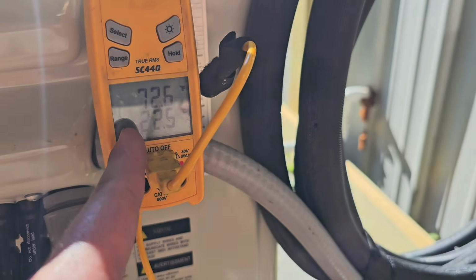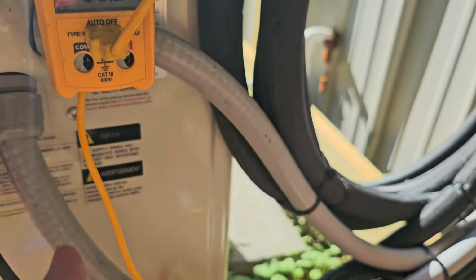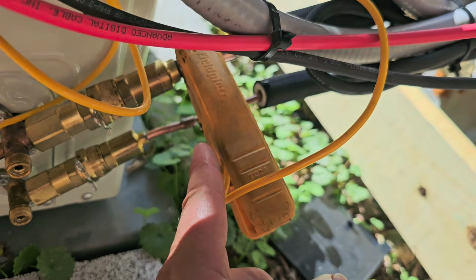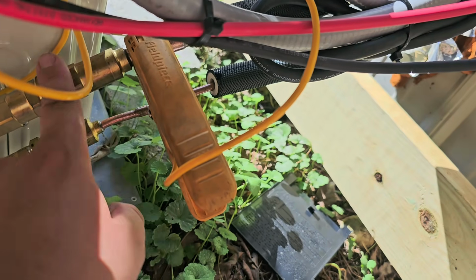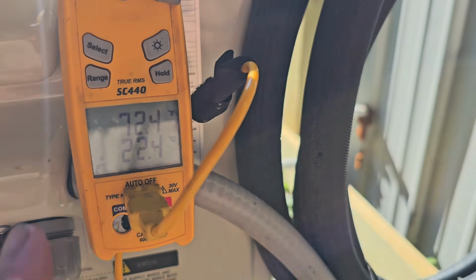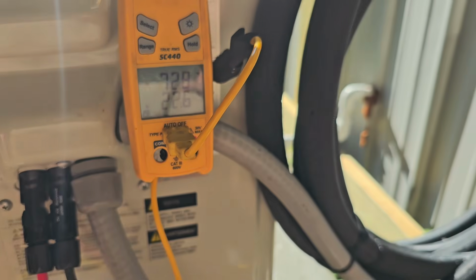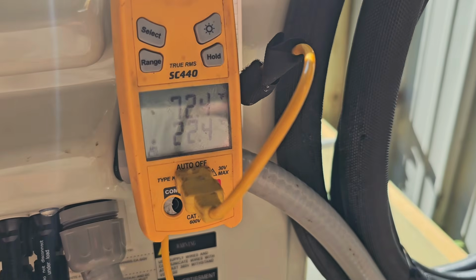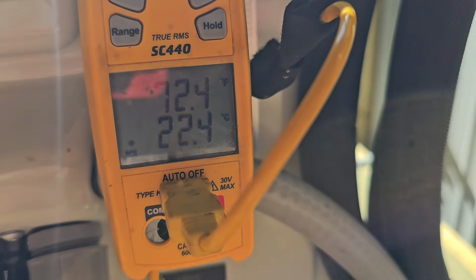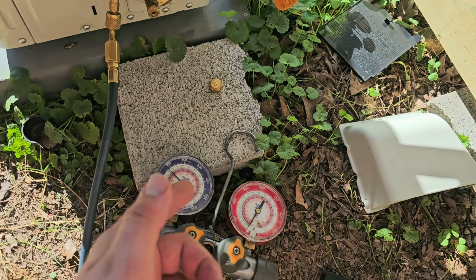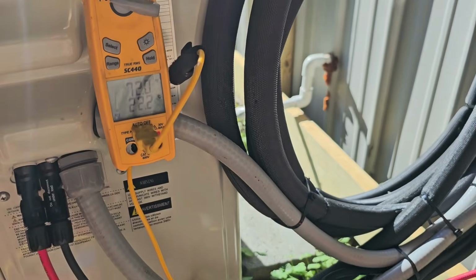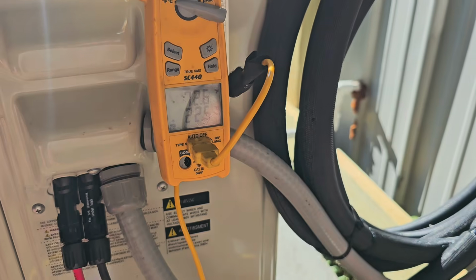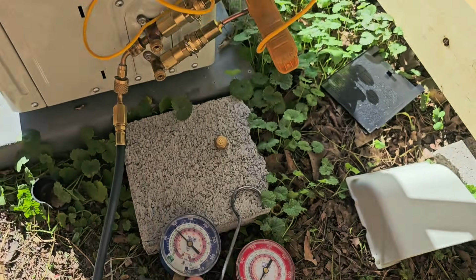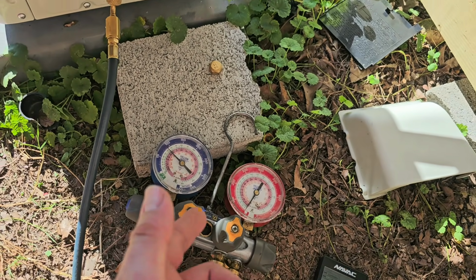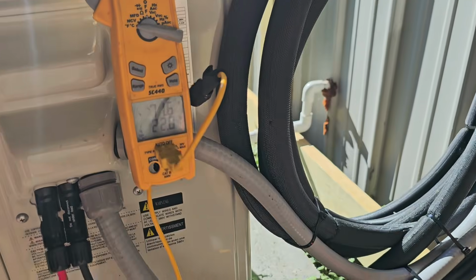Then you take that number and you subtract it from the number for your suction line temperature. So this is our gas line temperature or suction line temperature. It went from 86 to 72. That means our temperature inside is going to be lower on that supply air. And if you take 72 and you subtract 23, then you've got about 50 degrees of superheat. And we want to make that 10 degrees of superheat. So what do we do? We add more refrigerant.